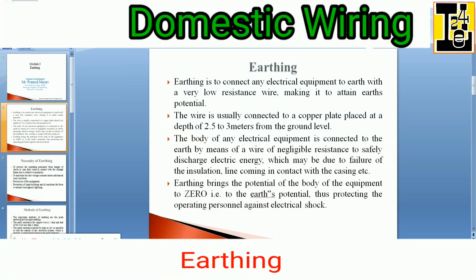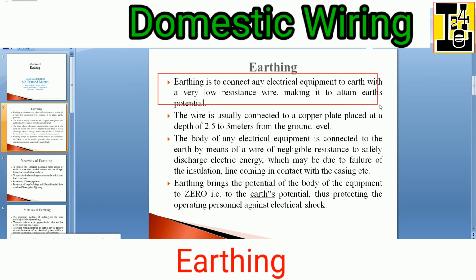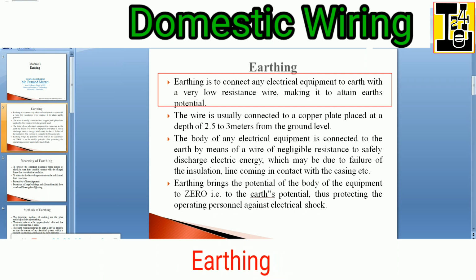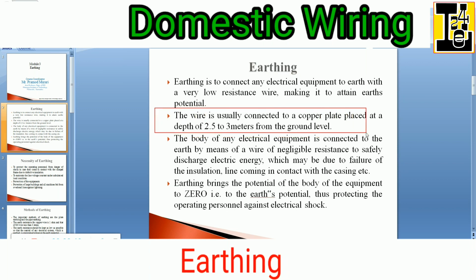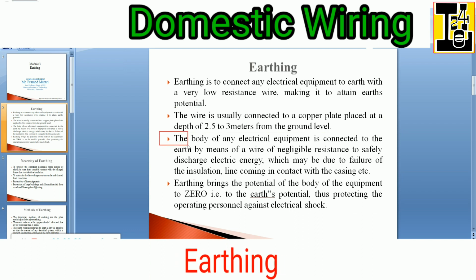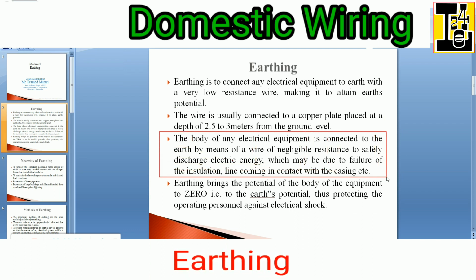Let us go through what is meant by earthing. Earthing is to connect any electrical equipment to earth with a very low resistance wire, making it attain earth's potential. The wire is usually connected to a copper plate placed at a depth of 2.5 to 3 meters from the grounded level. The body of any electrical equipment is connected to the earth by means of a wire of negligible resistance to safely discharge electric energy, which may be due to failure of the insulation or a line coming in contact with the casing, etc.